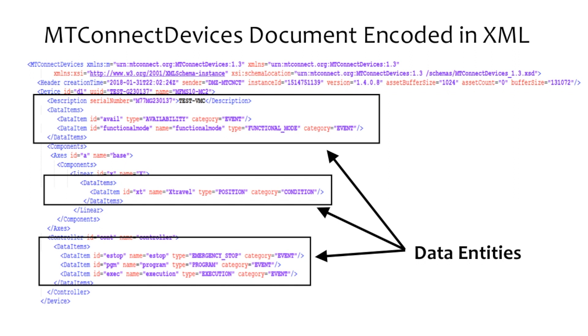Each piece of data can be characterized based upon a type and, when applicable, a subtype. Types include terms like temperature, pressure, controller mode, and execution state. Subtypes can further differentiate between similar but different pieces of data — for example, an actual position versus a programmed position. Additional information can be defined to enhance the meaning of values provided for data entities, including standard units where applicable, and definition of any preprocessing applied to the data, like determining an average value or maximum value for a series of data samples. The information model defines many other terms that may be used to define a piece of data.